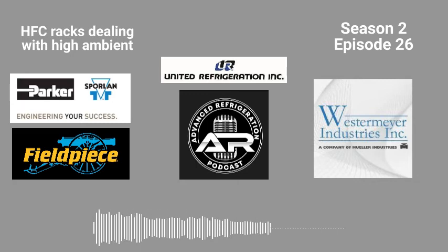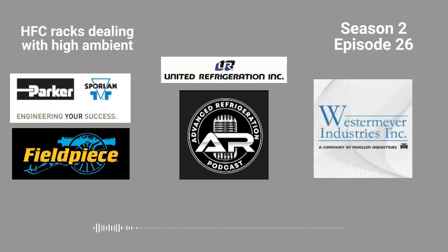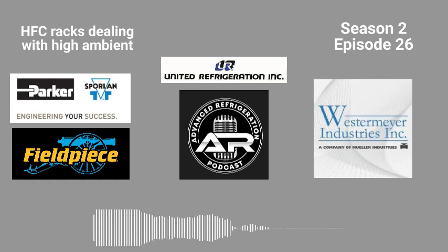Same thing with any of the compressors, the scrolls that have the vapor injection. It's imperative to make sure those things are running. The heat of compression that is reduced by the vapor injection scrolls is tremendous. So making sure that those subcoolers are working on those racks will help the head pressure tremendously.